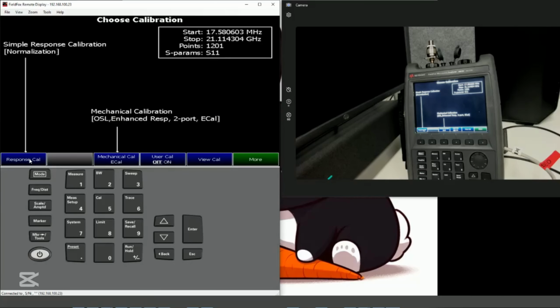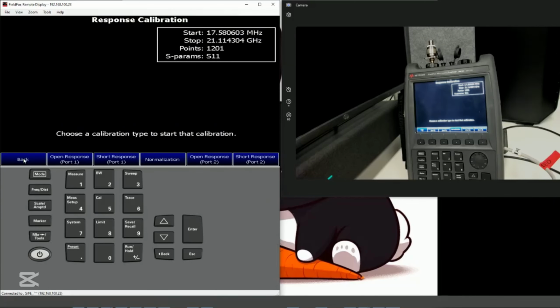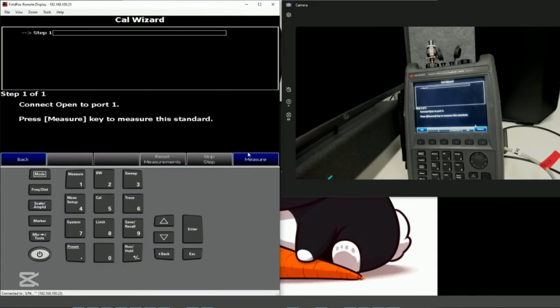Let's go to cal and response cal. So response cal is the quick and easiest way. It's not the most accurate, but it does give you some idea of how it works. So if you have a mechanical cal, then by all means go with that. But if you are out in the field and forgot to bring the cal kit, and you only have a response cal, I will go with that. So we have open response and short response, and this for port 2. So currently the connector is open port, so I'll go with open response and measure.